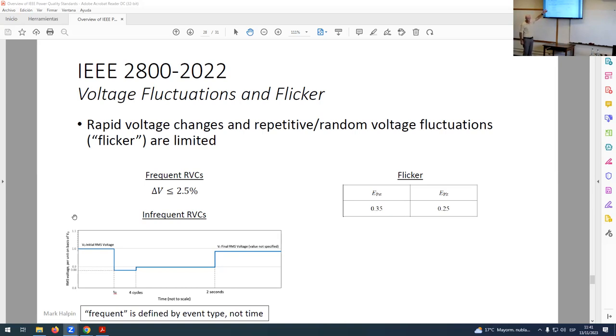And also, we defined in 2800 a distinction between so-called frequent rapid voltage changes and infrequent rapid voltage changes. Now, what frequency? That kind of implies time. You know, when I read something like this, frequent, okay, it occurs 5 times a day or 10. That's kind of what I think about when I hear frequent or infrequent. No, we didn't do it that way. Frequent or infrequent is defined by the type of event. For example, a transformer inrush event associated with normal operation of the equipment or the facility, that's considered a frequent event. An outage for maintenance or something like that, some kind of equipment change or configuration change, that's considered an infrequent event. So it's the type of the event rather than its rate of occurrence.